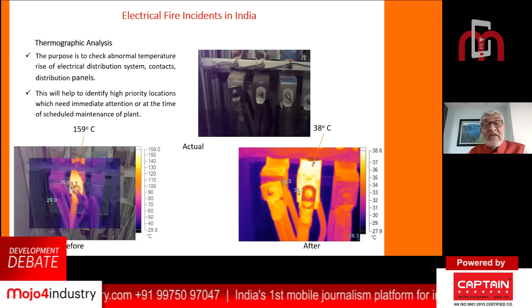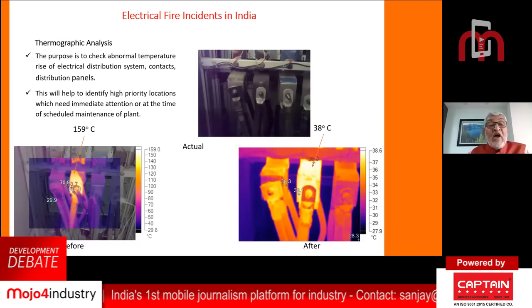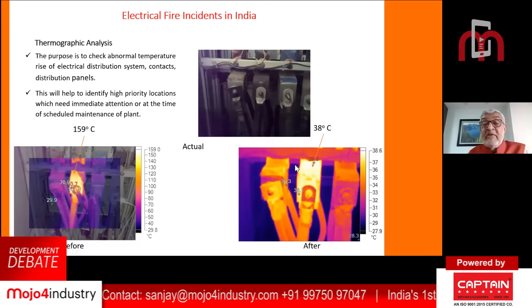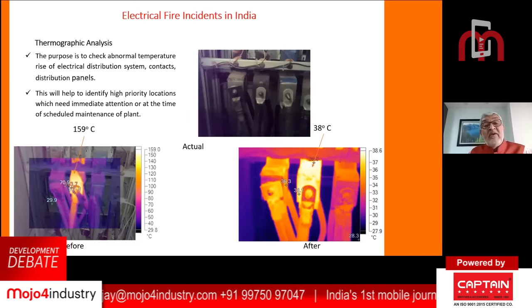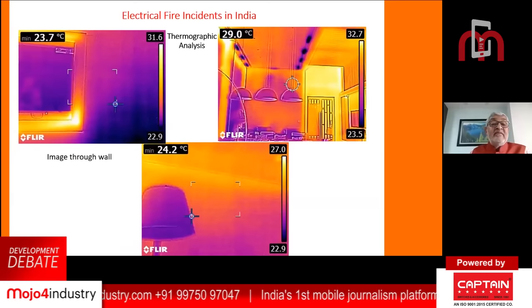When we went to this five-star hotel, we could see a 159 degree temperature on the terminals. They were loose, and we just tightened it, and the temperature came down from 159 to 38. So thermographic analysis is a fantastic tool.